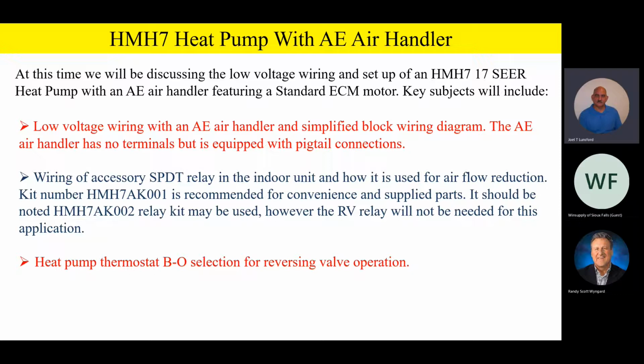And please make a note of this. You have to use the 002 kit on a variable speed product. And we'll talk a little bit more about that later. I like to look at that 002 kit as almost like a universal kit in the fact that you can use it for anything, but you have to have it for the variable speed. And if you don't have the 002 kit, you can still use the 001 kit, which just has a single relay for the standard ECM motor products. An example would be an AE air handler, or a TME furnace, or a TMY furnace. Those just use standard high efficiency ECM motors, and so you'd use the 001 kit.